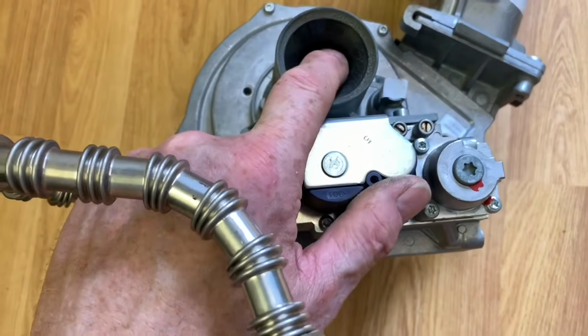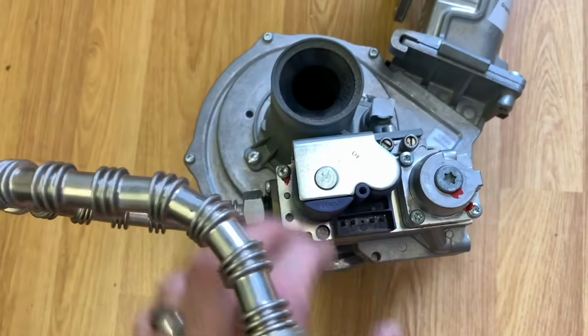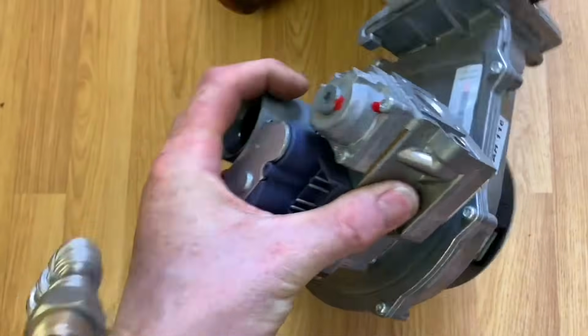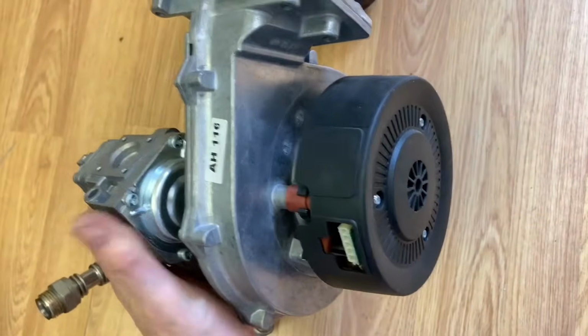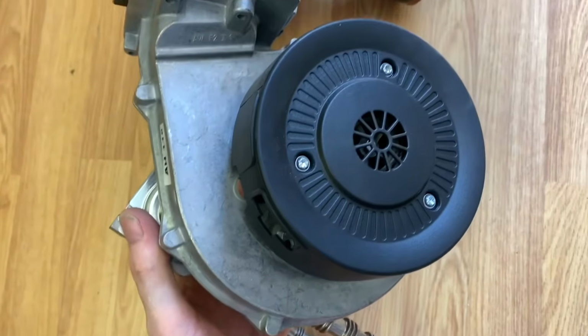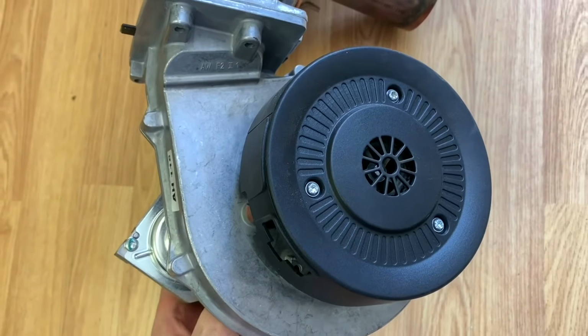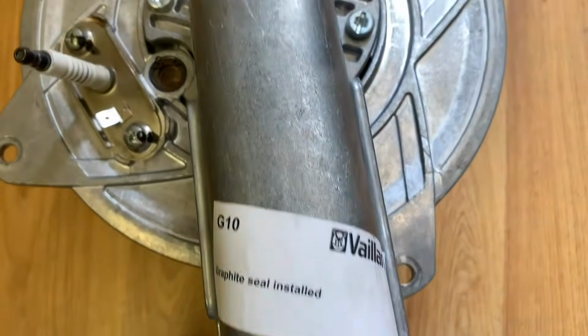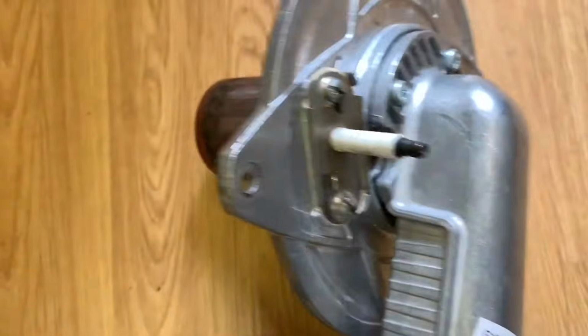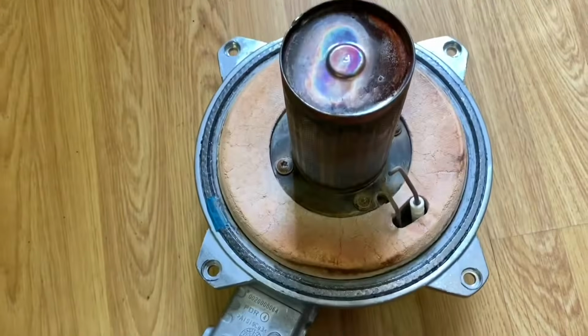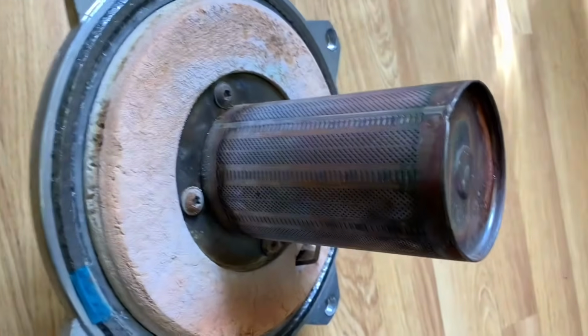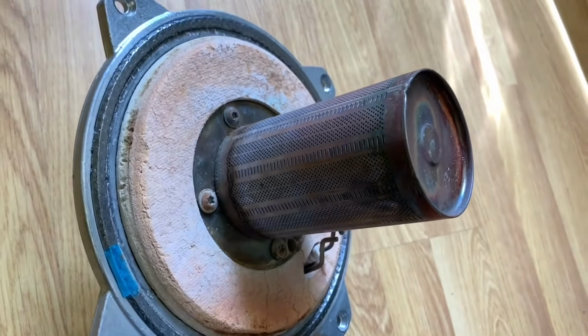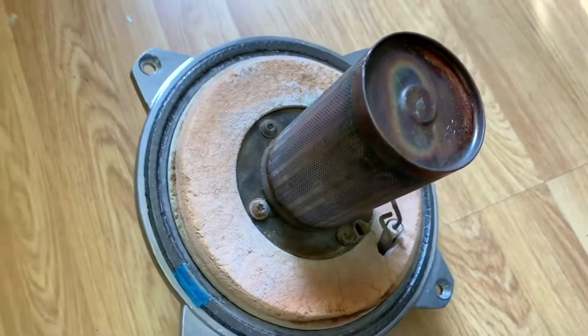This is where our air comes in for combustion, so this is where our silencer connected, and it connects all onto the fan. So this is the fan, you can see here, which is then the speed of the fan, like I said, draws in the gas into this blending tube. So if I flick it over, you can see the burner now. So you can now see the cup burner more closely. So again, burns 360 degrees.